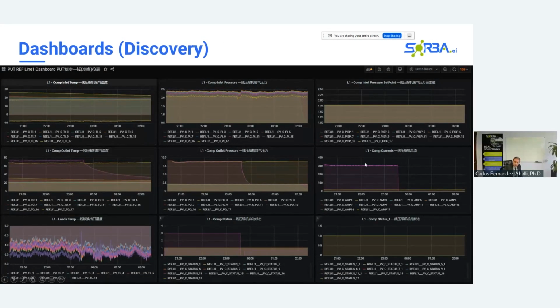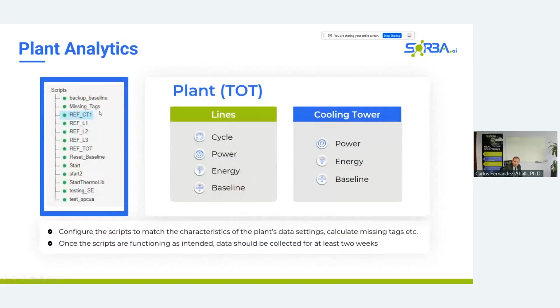Once you've confirmed that all your measurements are adequate, you can go ahead and configure all your scripts. In SORBA, in the refrigeration application, these are already made for you and just require simple modification. The way the scripts work, it looks at the cycle parameters, so all the enthalpies and all the pressures across the cycle. It then does a power calculation to determine the instantaneous efficiency, and then does an energy calculation to be able to build a baseline for a determined performance, not in every instance, but over a period of interest.